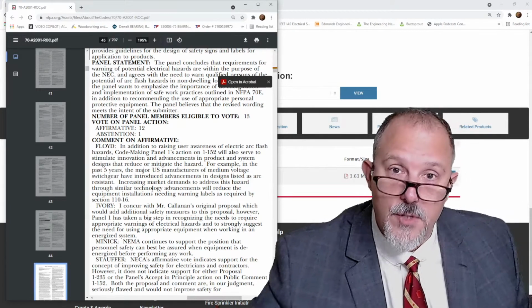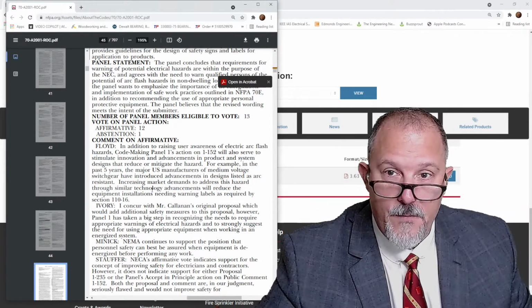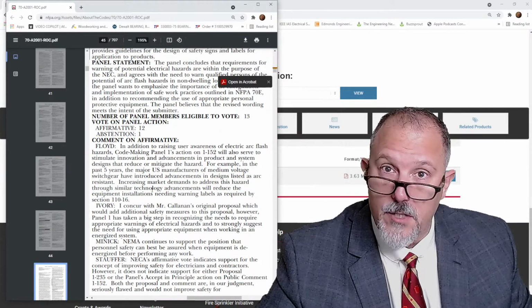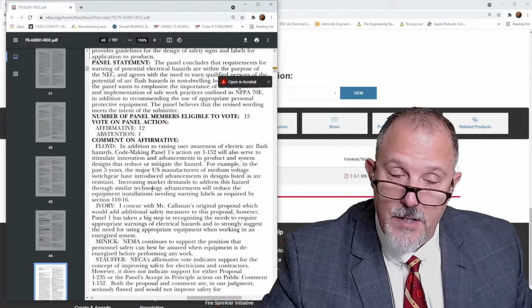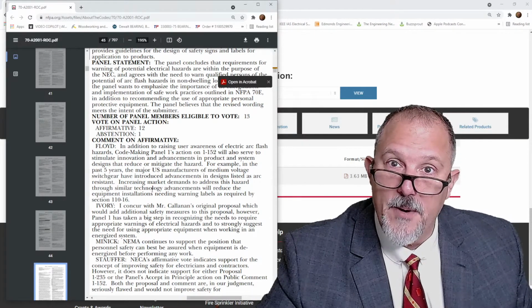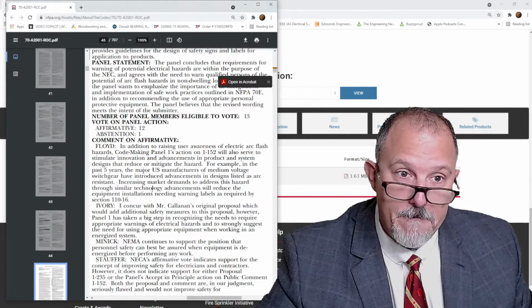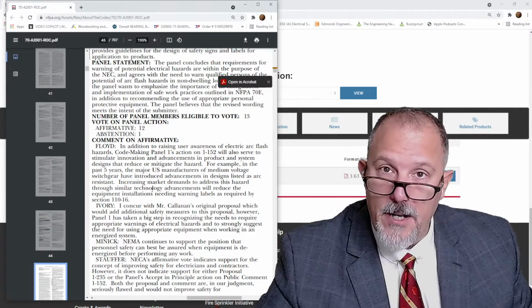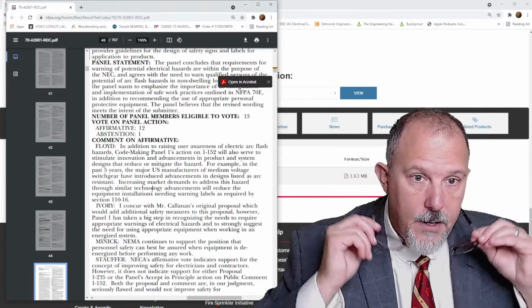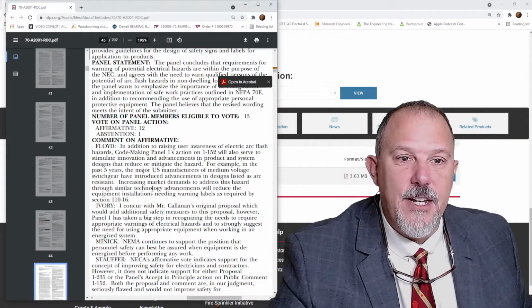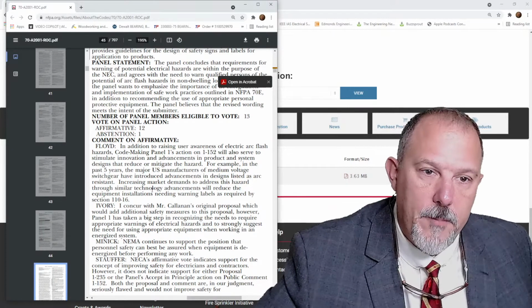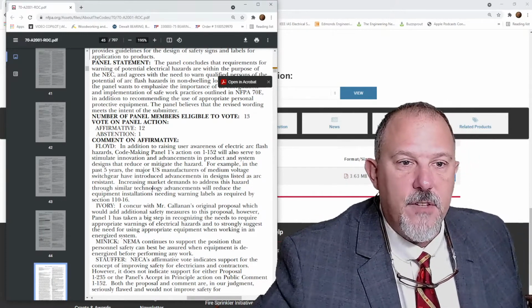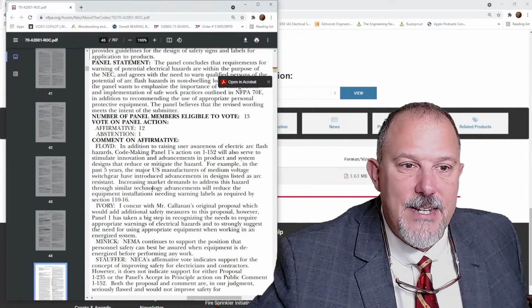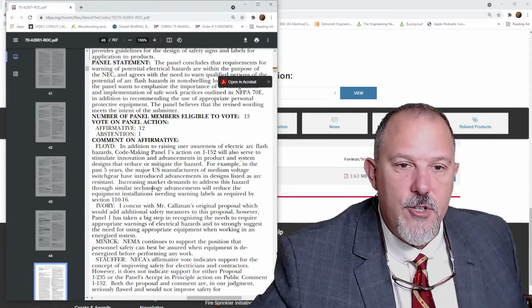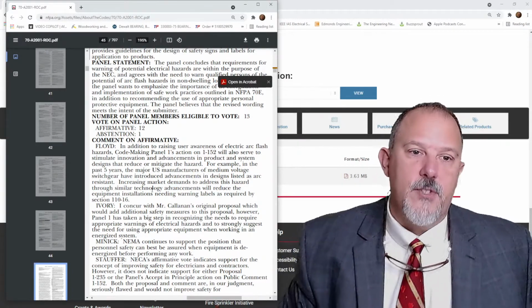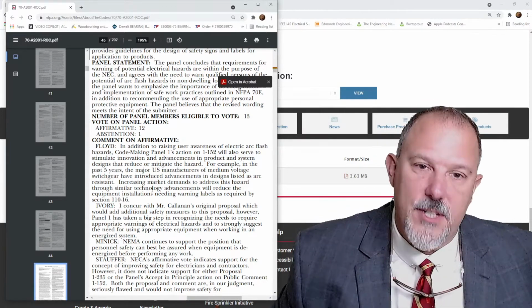But Lanny is one of those individuals in the industry, an electrical engineer that worked for DuPont, and he's still around, and he's still heavily involved. Hasn't decided to set down any reins. He's very active in electrical safety. Great guy. So he commented on the affirmative, stating 1-152 will also serve to stimulate innovation and advancements in product and system designs that reduce or mitigate the hazard. Past 5 years, the major U.S. manufacturers of medium voltage switchgear have introduced advancements in designs listed as arc resistant, increasing market demands and to address the hazards through similar technology advancements will reduce the equipment installations needing warning labels as required by 110-16.